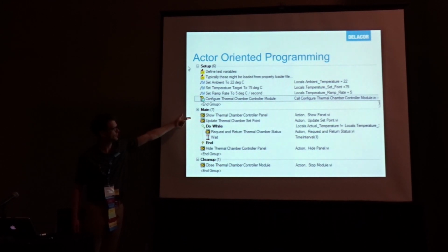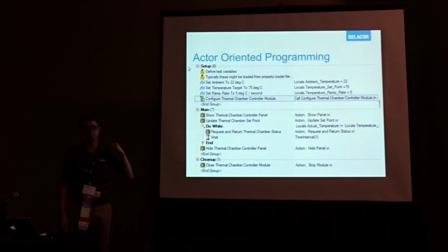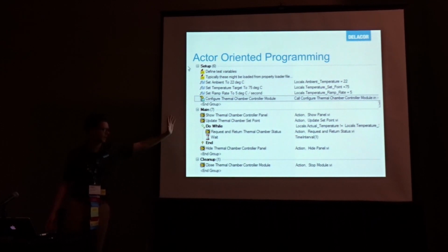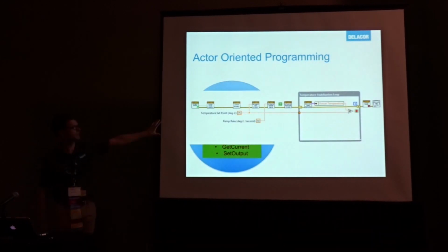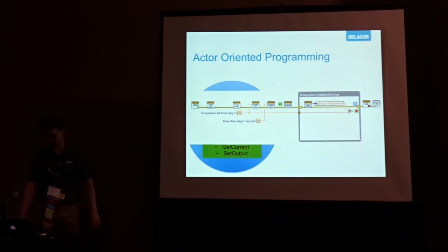So show the thermal chamber front panel, update the set point, and then request and return the status. Tell me what your status is, tell me what your temperature is. And I'm doing that until it reaches the target set point, and then I'm closing the thing down. I'm doing exactly the same as I am with that LabVIEW VI.